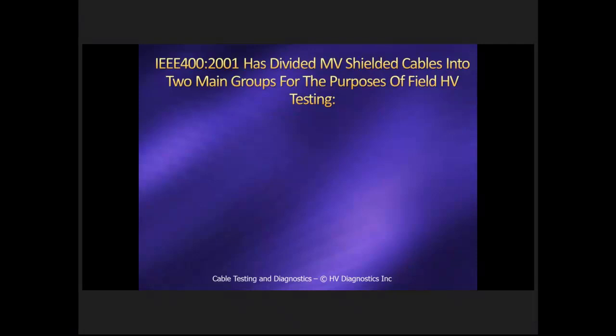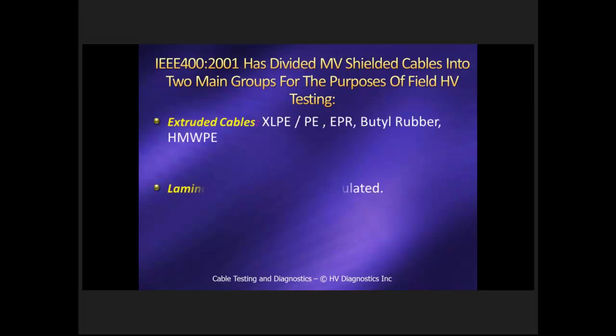If we look at the IEEE 400, it has divided medium voltage shielded cables into two main groups for our purposes of field testing. The first group is extruded cables. I would imagine most people on the conference call would really be testing those types of cables. The grouping includes XLPE, which is cross-linked polyethylene, the EPR compounds, and they're varied compounds from different manufacturers, butyl rubber, which is an older compound that is no longer used but can be found in the field. And another predecessor to the XLPE is high molecular weight polyethylene. That's another type of material that is all grouped together and extruded. And most people will be testing extruded cables.